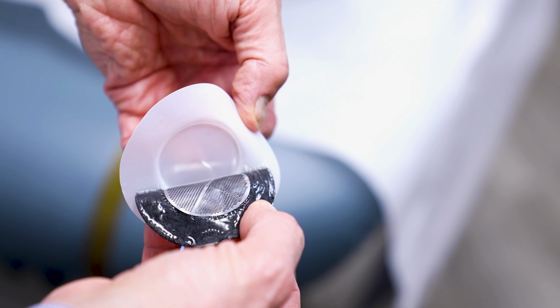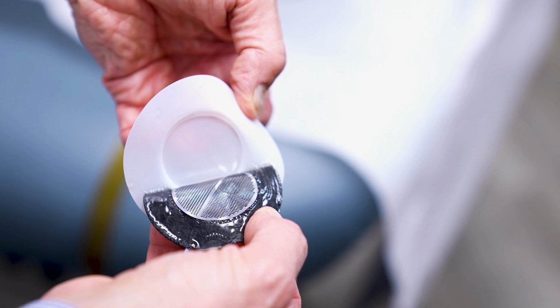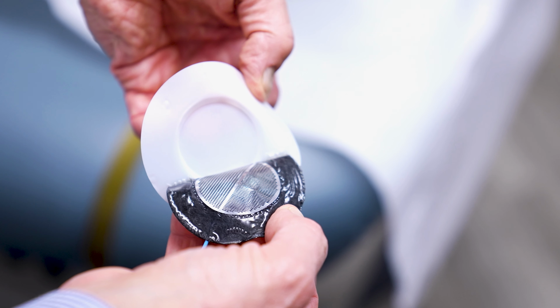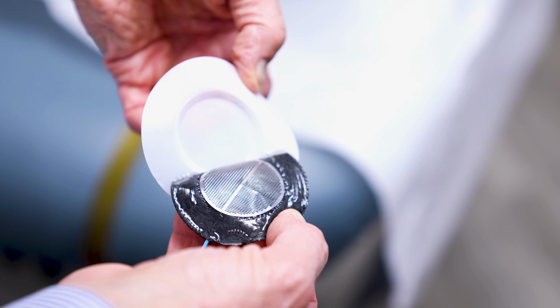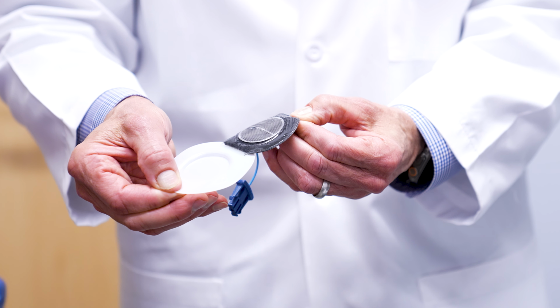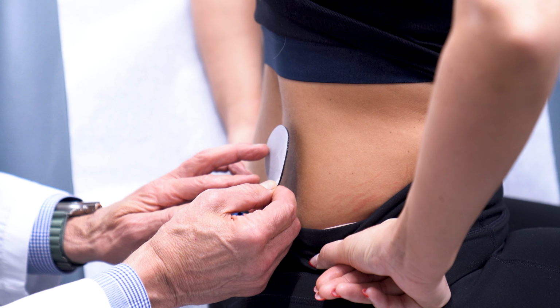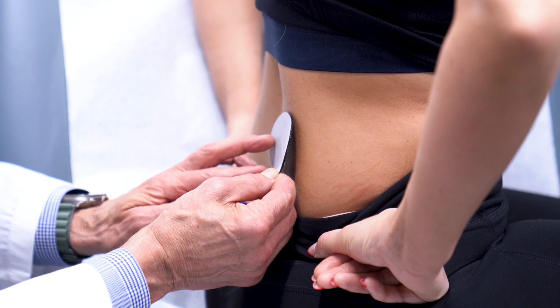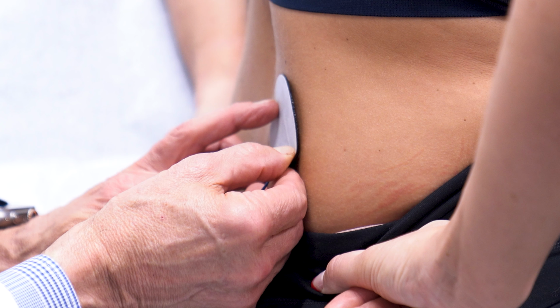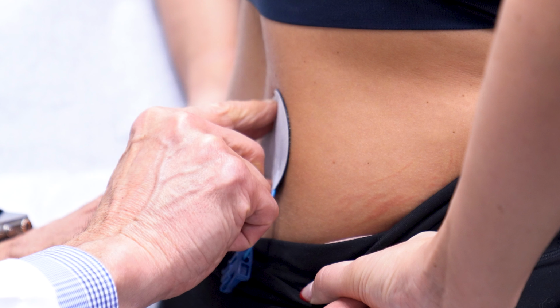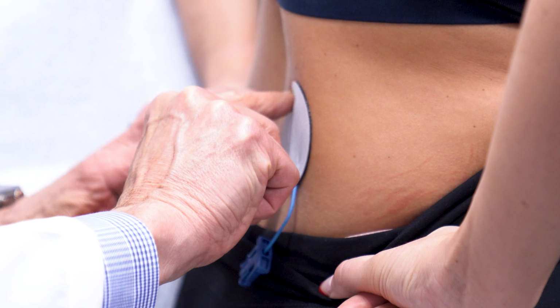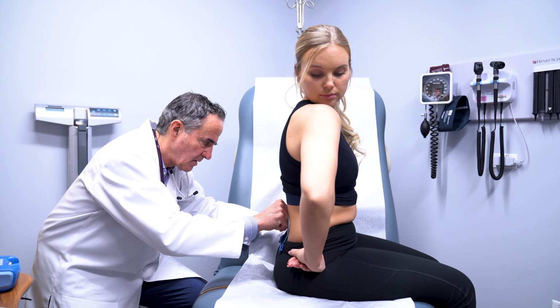Carefully, slowly, and gently peel the first electrode off of its protective cup, preventing any kinking of the metal array and avoiding any contact with the microneedles. Place the first electrode directly over the marked site. Apply pressure over the hydrogel around the outside perimeter of the electrode to keep it in place. Repeat this process with the second electrode. Maintain at least 1 inch of spacing between the edges of the electrodes. The edges cannot touch or the patient can receive a burn.